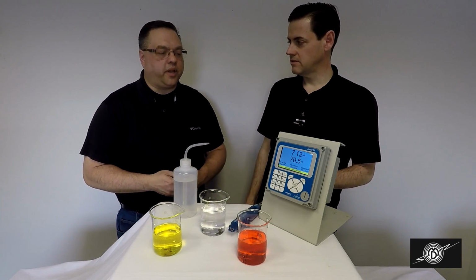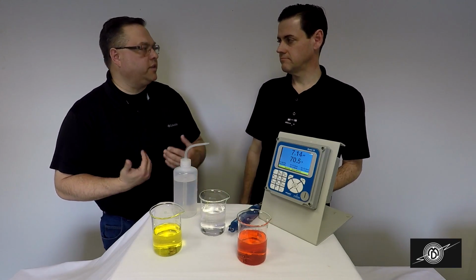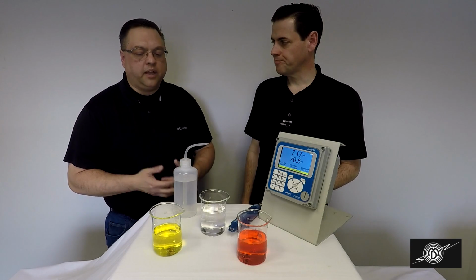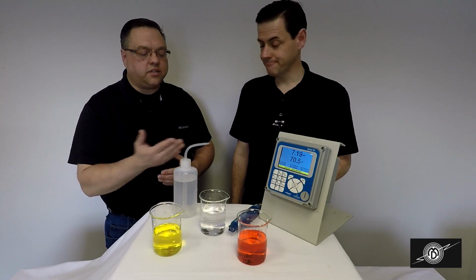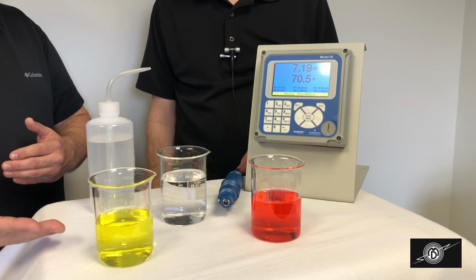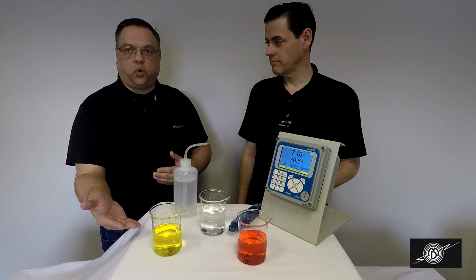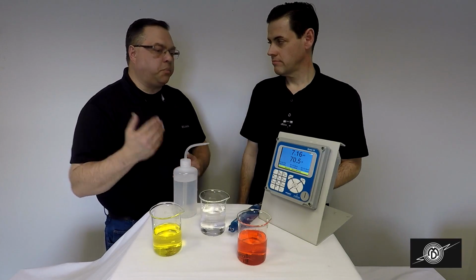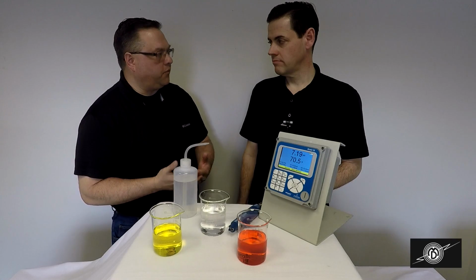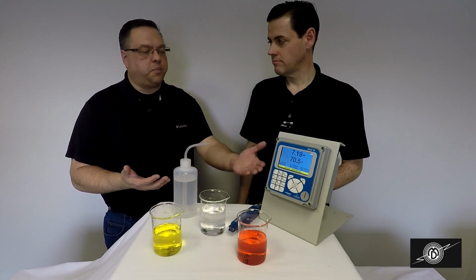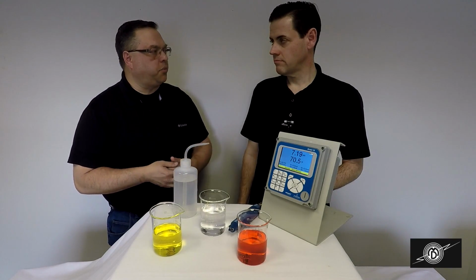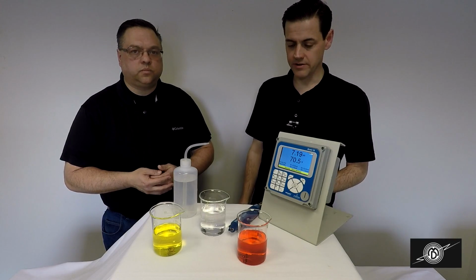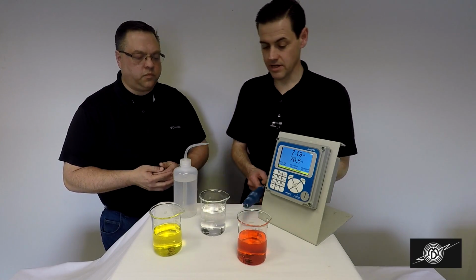You want to do a 2-point calibration because you need to zero and span every instrument. In the case of pH, the sensor sees a millivolt signal. pH 7 is approximately 0 millivolts. pH 4 is approximately 180 millivolts. So you want to zero and span the instrument so it's ready for use in your process. Okay, so the first step you said was to clean the sensor?